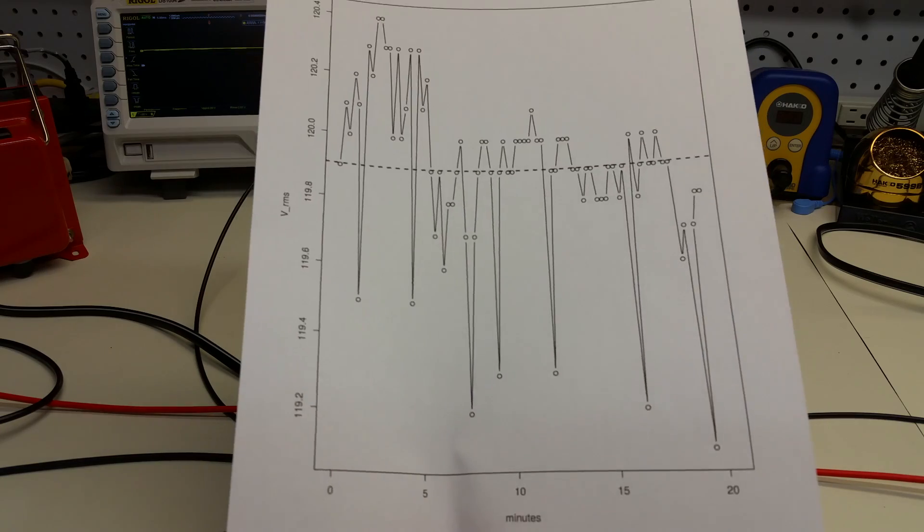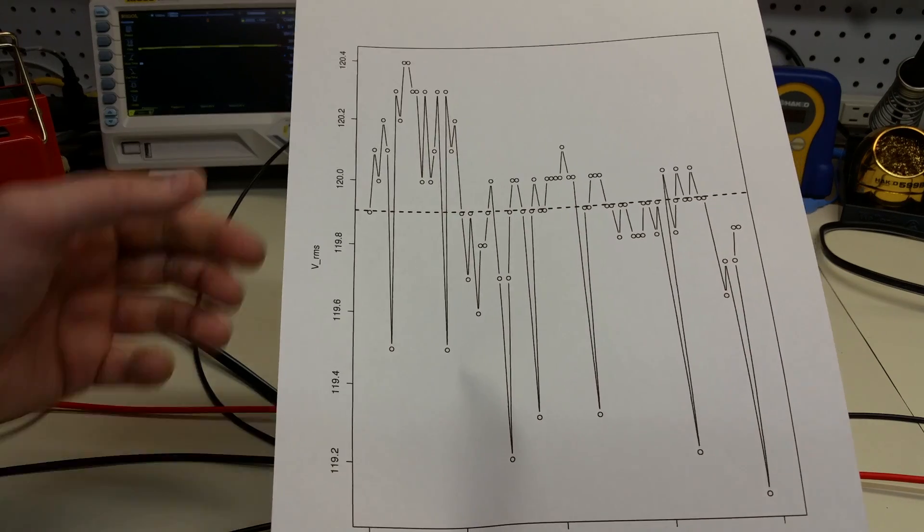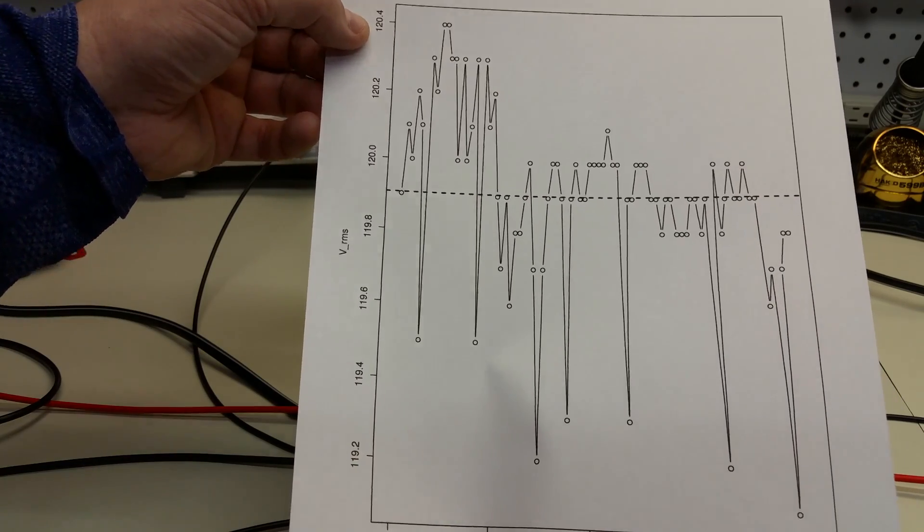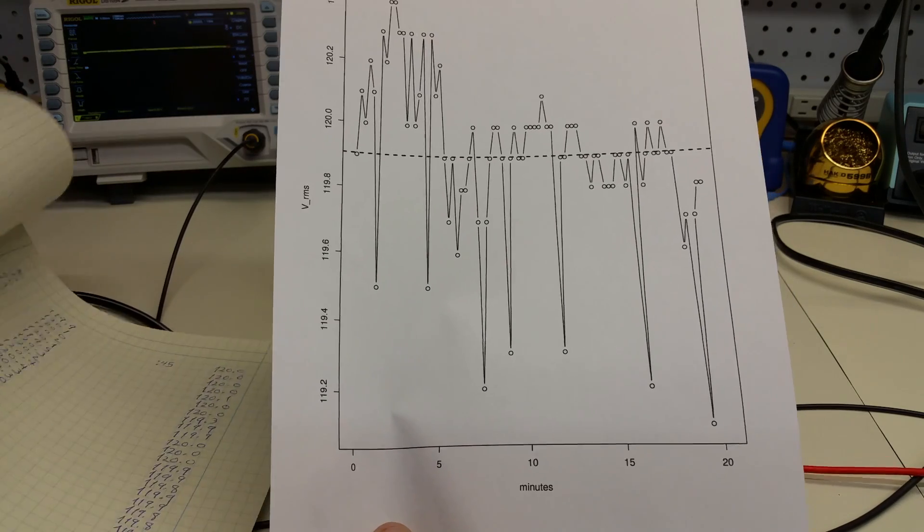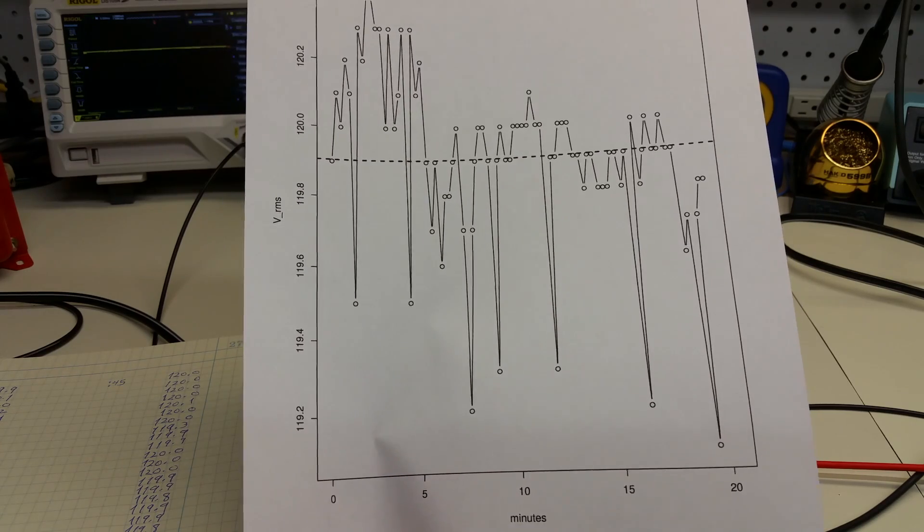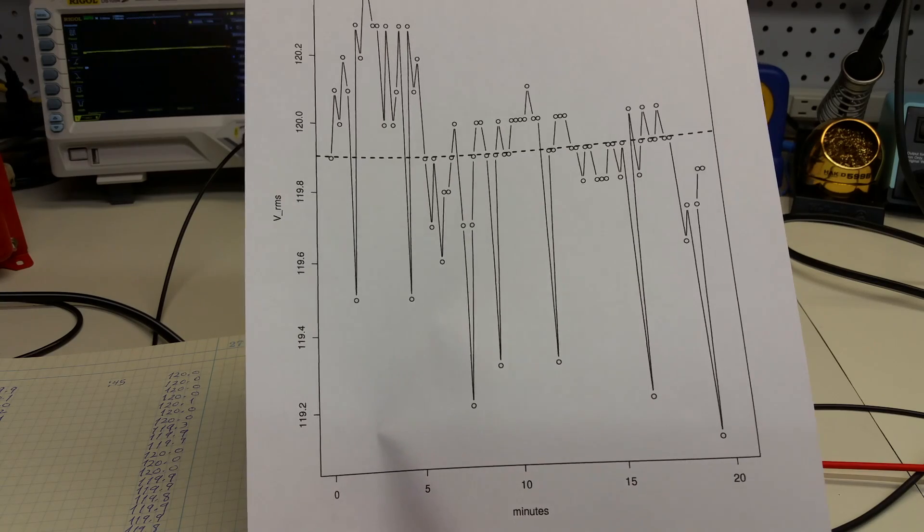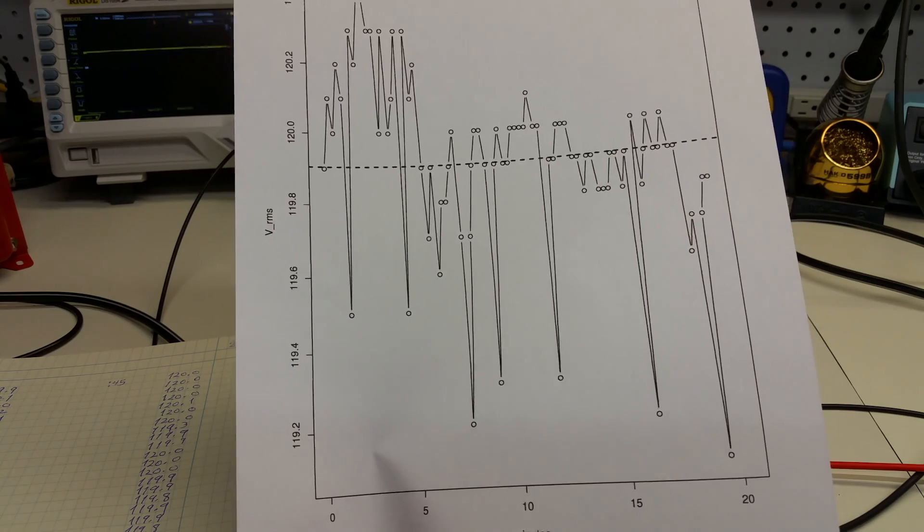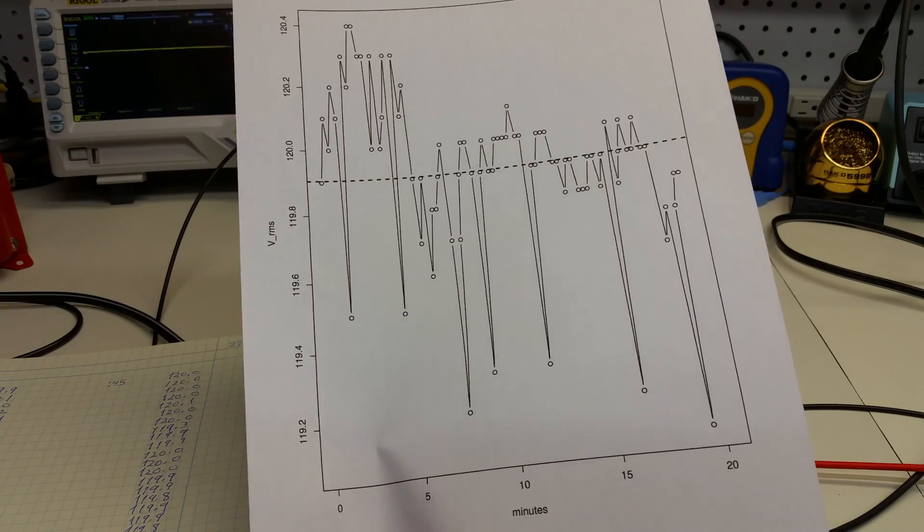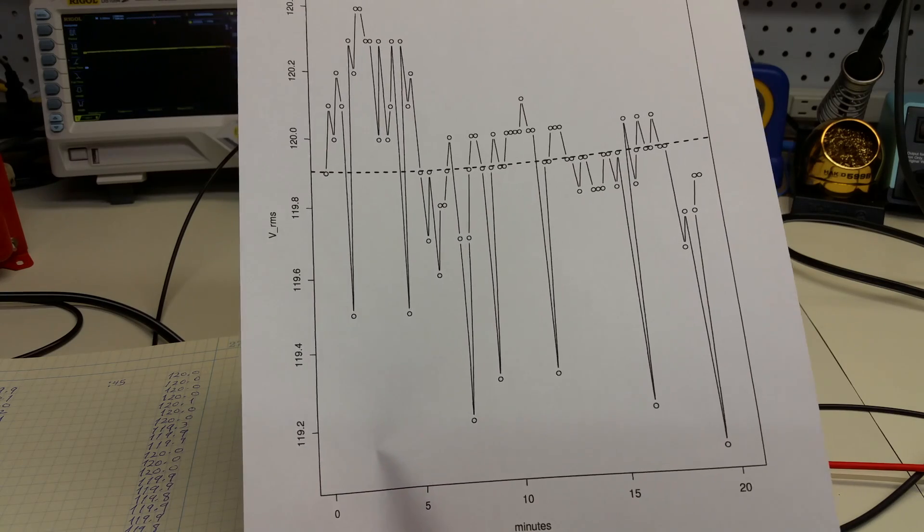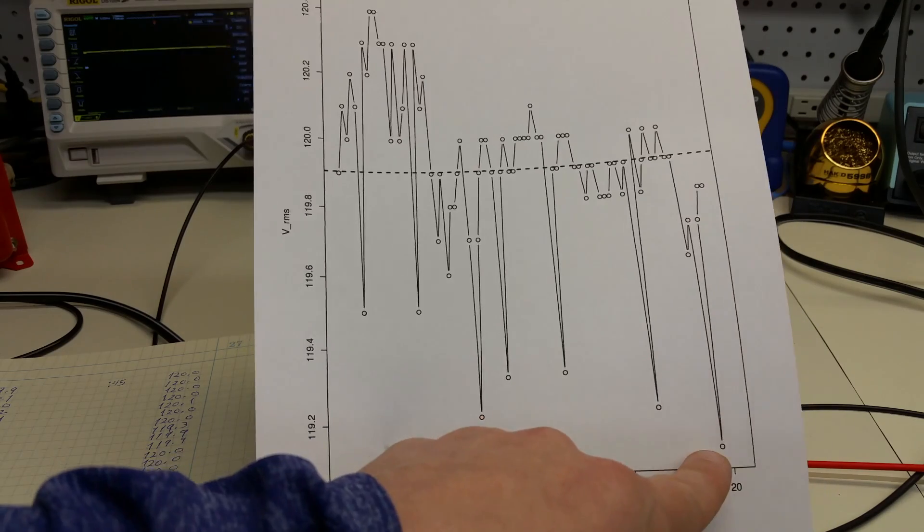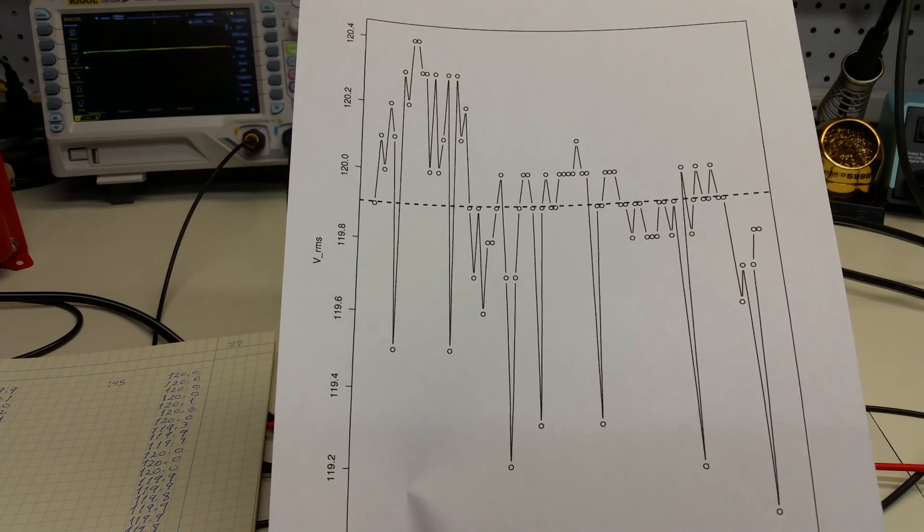So let's look at the data a little bit differently. This is the data plotted out in R. And you see that it's very all over the place. So it's variable over time. The axes here go from 119.2 volts RMS to 120.4. There's this average running through here. And the statistics of this time series, when you compute them, are the mean, which is the dotted line, is 119.9 volts RMS. And the median is the same. It's 119.9. Which means that 50% of the data fall above this line and 50% of the data fall below that line. The standard deviation here is a quarter of a volt. And the minimum reading is 119.1 volts down here. And the maximum reading, and there's two of them up here, is 120.4 volts.